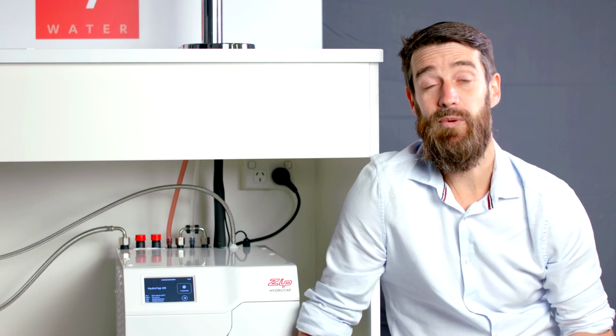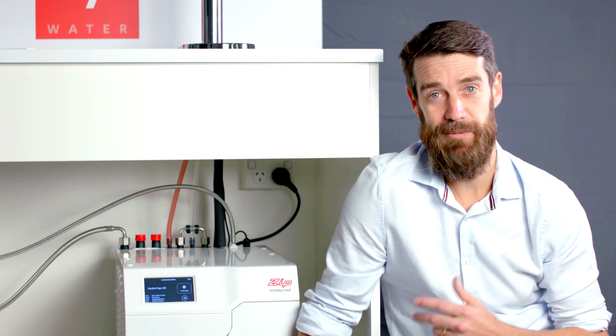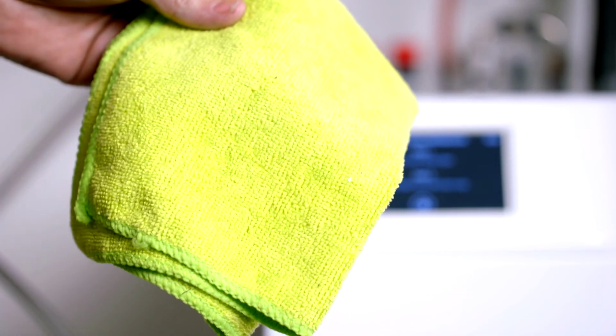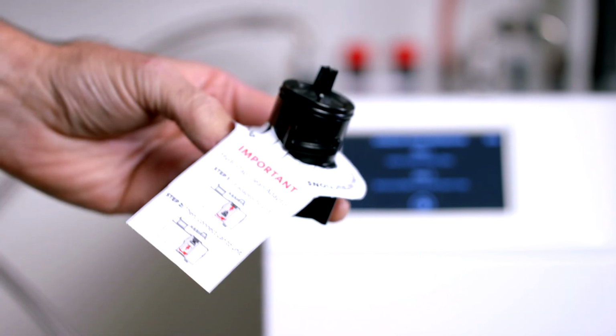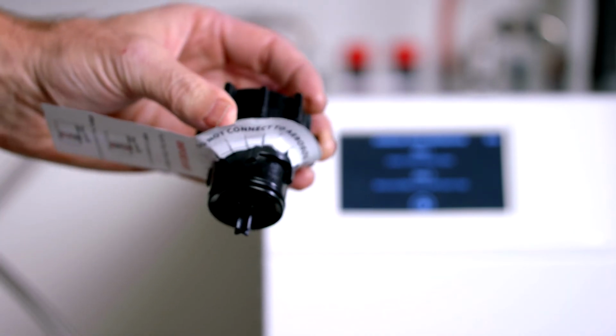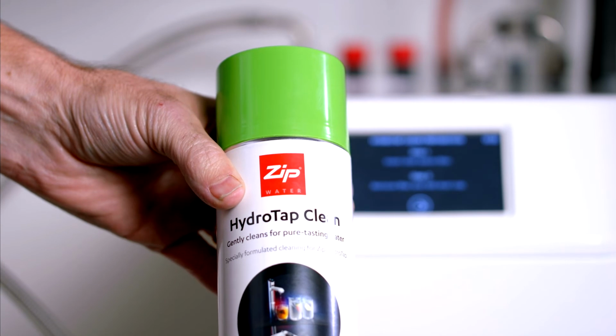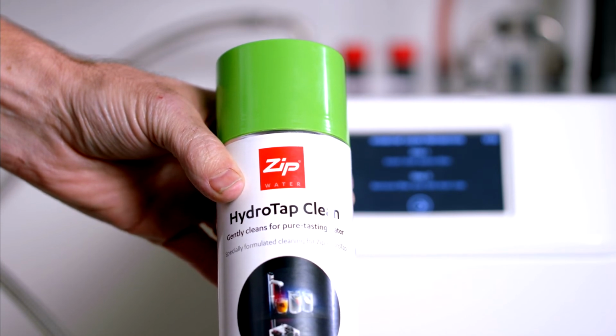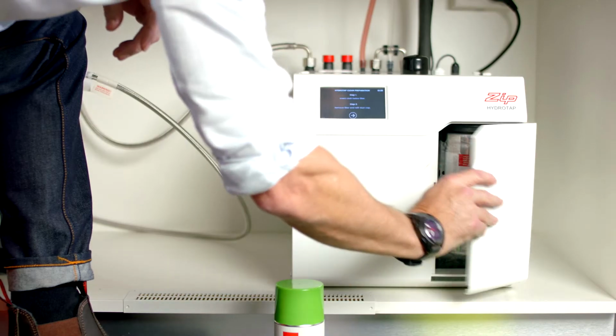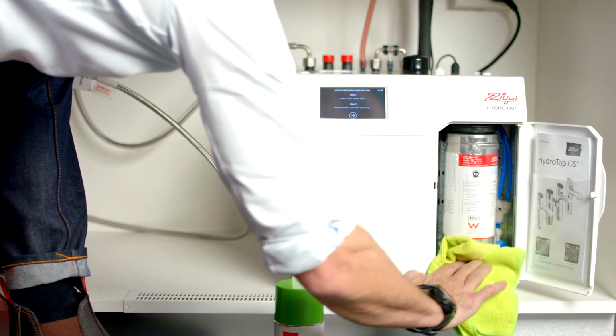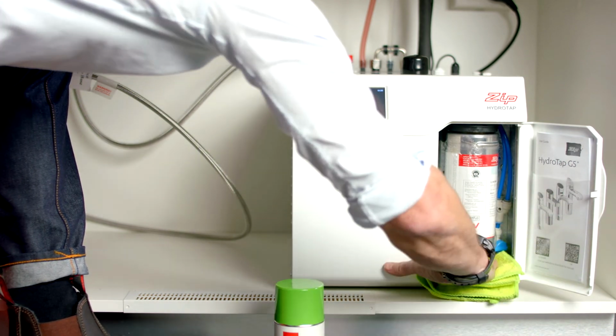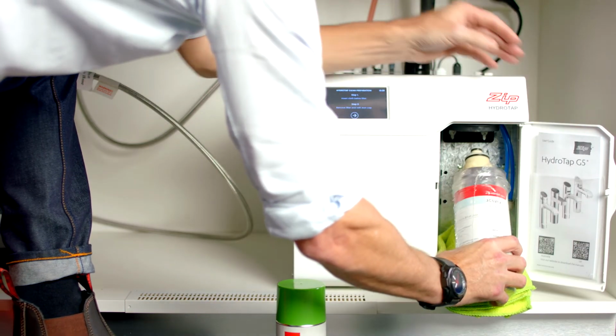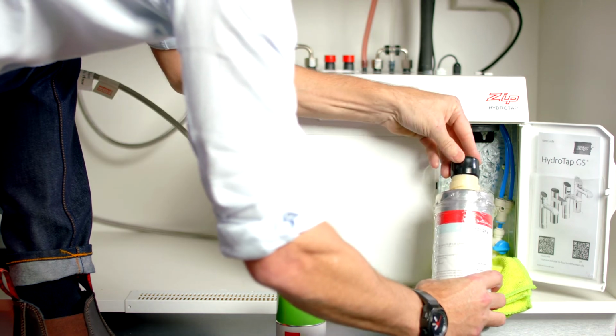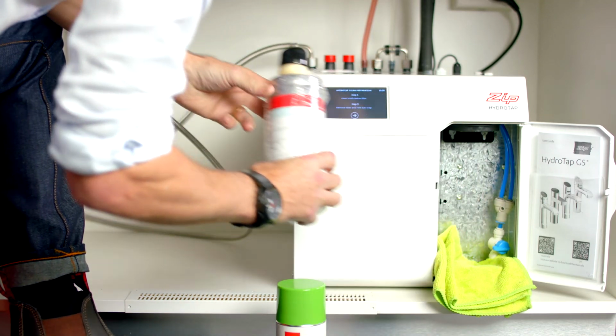Once complete, we need to prepare for the HydroTap Clean process. You'll need a microfiber cloth, HydroTap Clean adapter and a HydroTap Clean can. Both the adapter and HydroTap Clean can are supplied with the HydroTap Command Center. First, fit the cloth underneath the internal filter. This is to catch any water that may spill in the HydroTap when you remove the filter. Next, remove the filter, and once removed, refit the dust cap of the filter to keep the filter protected.